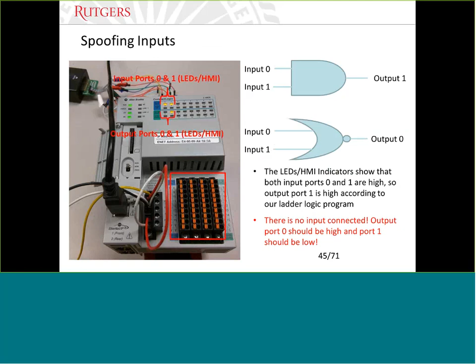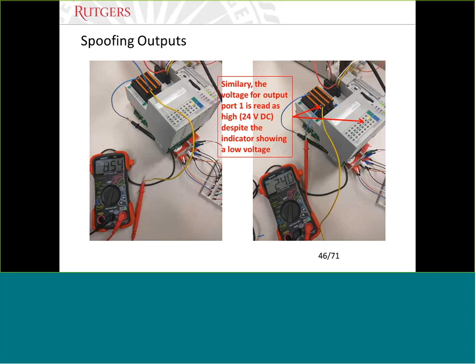For spoofing the outputs: in the first case, we attached the voltmeter to output port 0 and it shows a low voltage of 8.54 volts, however the PLC believes the indicator shows a high value for output port 0. Similarly, the voltage for output port 1 is read as high, 24 volts, but the LED indicator shows a low voltage.